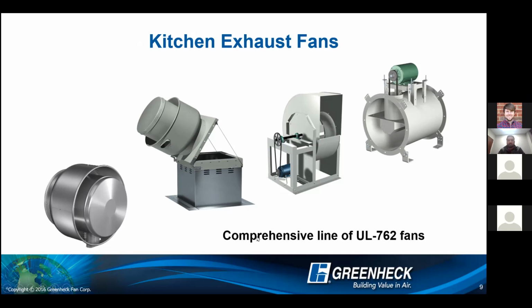Keep in mind that code is going to state that the discharge height of the wind band of the exhaust fan needs to be 40 inches above the roof deck. One common thing that I'll see missed is that people forget to calculate the fact that there's going to be 2 or 3 inches of insulation on the roof. So then they have their wind band at exactly 40 inches, when with that insulation, it's actually more like 38. It can be fixed if you get called out for it with a wind band extension, but that's just a common thing to consider.